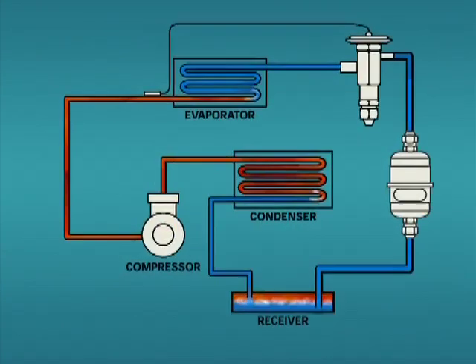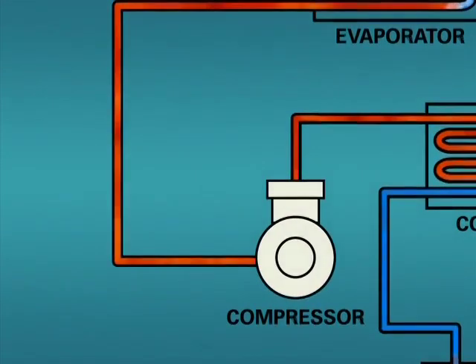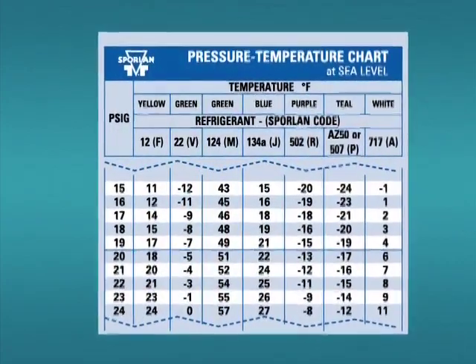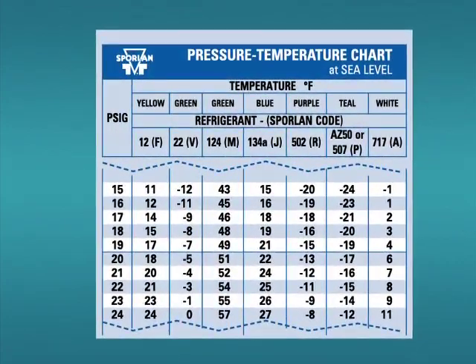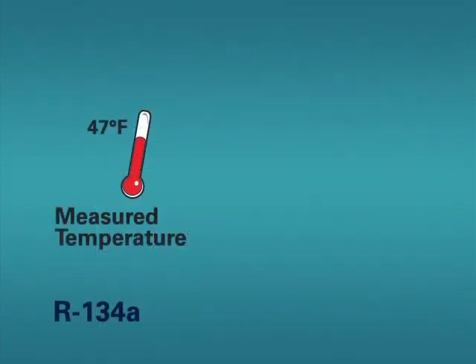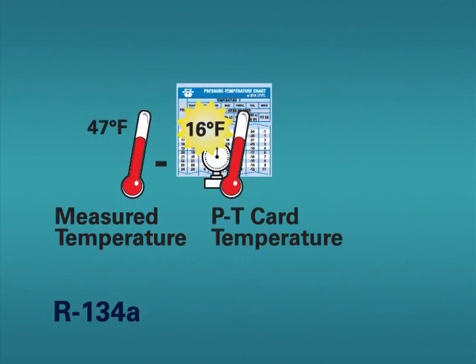As a second example, let's take readings at the compressor inlet. Our pressure gauge reads 16 PSI and our measured temperature is 47 degrees Fahrenheit. To calculate our superheat, we again reference our PT card. 16 PSIG on the PT card indicates a temperature of 16 degrees Fahrenheit. The difference between 47 degrees Fahrenheit measured temperature and 16 degrees Fahrenheit from the card is 31 degrees Fahrenheit superheat.